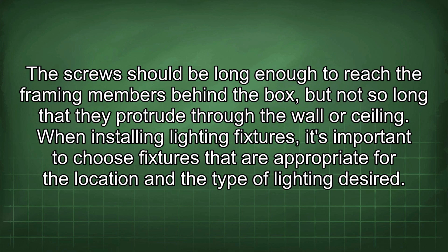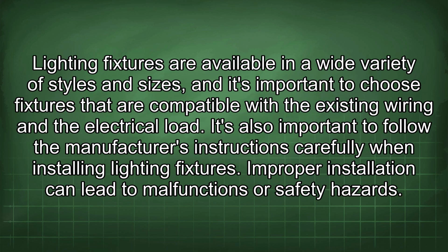When installing lighting fixtures, it's important to choose fixtures that are appropriate for the location and the type of lighting desired. Lighting fixtures are available in a wide variety of styles and sizes, and it's important to choose fixtures that are compatible with the existing wiring and the electrical load. It's also important to follow the manufacturer's instructions carefully when installing lighting fixtures. Improper installation can lead to malfunctions or safety hazards.